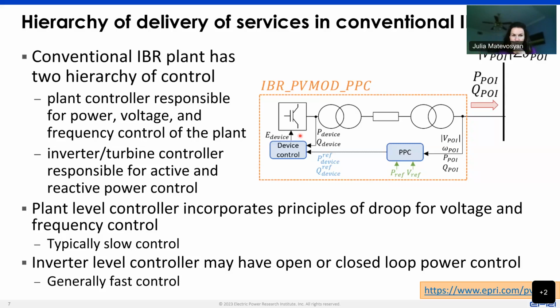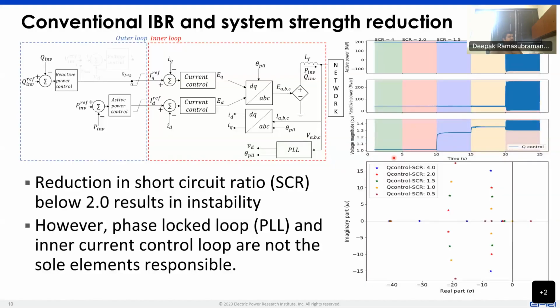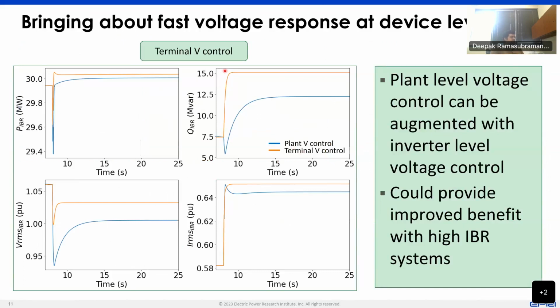Yeah, so one of the things there is we do have to be careful, because we also don't want to impose a certain method of hierarchy of control on manufacturers. We have heard of certain plant developers who have very fast plant control, and they have been able to reduce the round-trip communication time delay, which means that they might be able to provide a lot of the services even though it resides at the plant level. So rather than saying where in the inverter control hierarchy it should exist, it might be more beneficial to define some of these services based upon how fast the service should be provided. And not just how fast, we can also translate this into the frequency domain to understand what kind of disturbance rejection properties and what bandwidth of control the entire plant has.